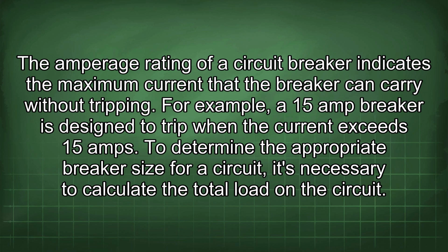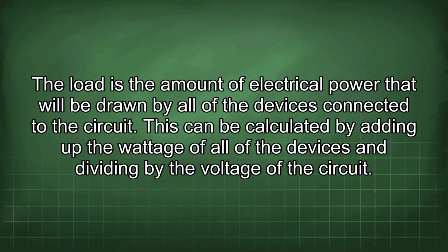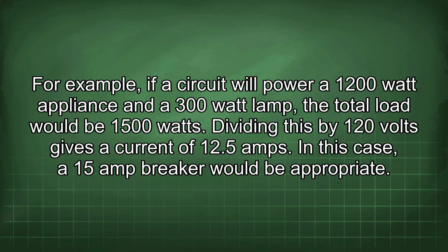To determine the appropriate breaker size for a circuit, it's necessary to calculate the total load in the circuit. The load is the amount of electrical power that will be drawn by all of the devices connected to the circuit. This can be calculated by adding up the wattage of all of the devices and dividing by the voltage of the circuit. For example, if a circuit will power a 1200 watt appliance and a 300 watt lamp, the total load would be 1500 watts. Dividing this by 120 volts gives a current of 12.5 amps. In this case, a 15 amp breaker would be appropriate.